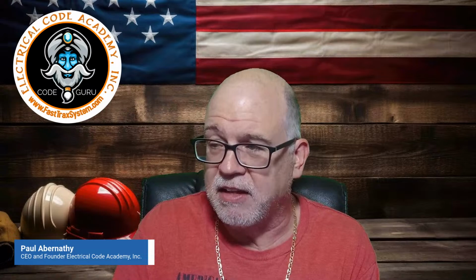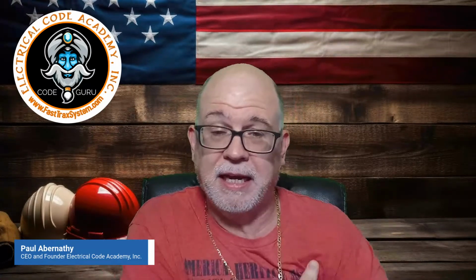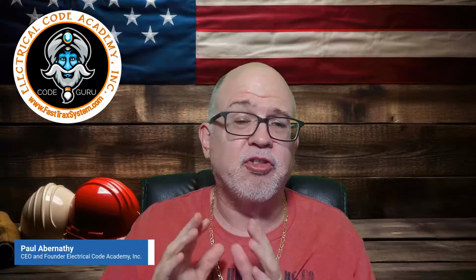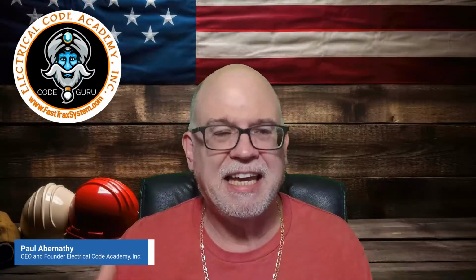2. That is so important too, because if you are calculating for somebody in the real world, you ought to know. For example, when I'm doing this 10,000 square foot calculation for the house that my brother's wiring back in Virginia, I know that they're going to have more than 2. So I have to look at it and say, well, it looks to me like we're going to have at least 5. So I have to take that as 1500 VA each for 5 of them, that type of thing, okay? And then when I'm calculating, I might do it at 6 after I've done everything and see if that's going to change my load any, or it's going to make my service change, just so I know that I have that flexibility. If I'm wiring it, I decide I want to put 1 more in there, that type of thing, okay? Makes sense? So I'm always thinking about that in the real world. The exam is pretty simple. They've got to give you the values to take into consideration, right? Okay. All right, so here we go.